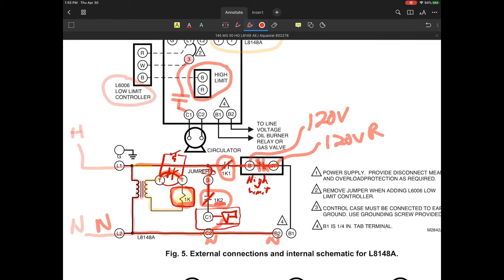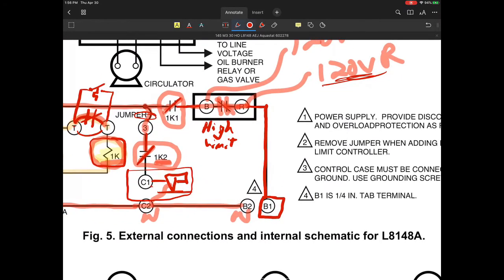So you're going to be supplying 120 volts at terminal B, and you're also going to have 120 volts at terminal R. But keep in mind, that's assuming the boiler water temperature is not up to temp. If it is up to temperature, then of course that would be de-energized and you would not have power there. Of course, from terminal R, that goes directly through the board tracing, and that'll go directly to terminal B1. This is usually the burner circuit that would power up some sort of, let's say, an oil-fired burner or a 120 volt transformer or something like that, that might be going to another circuit.